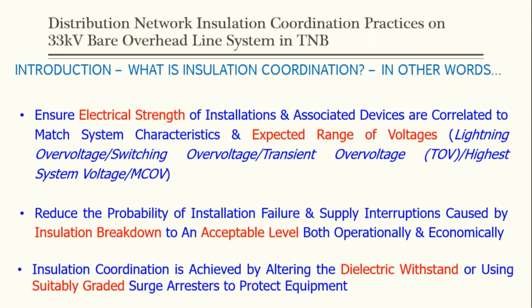It can also be said that insulation coordination is to reduce the probability of insulation failure and supply interruptions caused by insulation breakdown to an acceptable level, both operationally and economically. Okay, so the key here is we allow insulation breakdown, but to an acceptable level in order to protect the system. And insulation coordination is achieved by altering the dielectric withstand or using suitably graded surge arresters to protect the equipment. So those are some of the simple wording in terms of the definition given by IEEE and also IEC. Okay, so we are good here. So far, so good. All right.